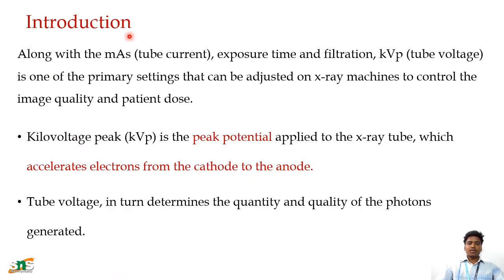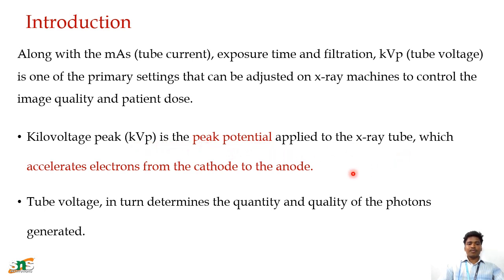Moving on to the introduction: along with the primary settings like tube current (mA), milliampere-seconds (mAs), exposure time, and filtration, tube voltage (KVP) is one of the primary settings that can be adjusted on X-ray machines to control image quality and exposure factors. Kilovoltage peak (KVP) is the peak potential applied to the X-ray tube, which accelerates electrons from the cathode to the anode. In summary, mA determines the quantity and KVP determines the quality of the photons generated.